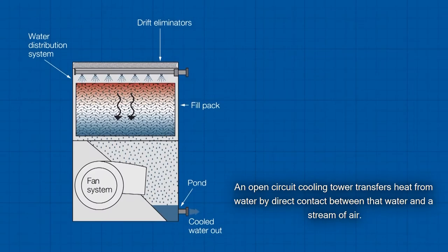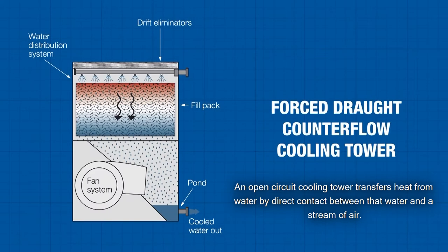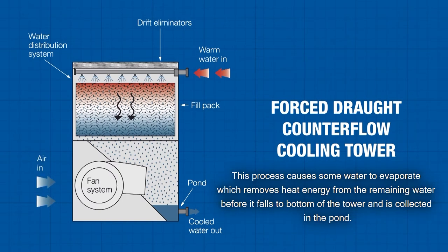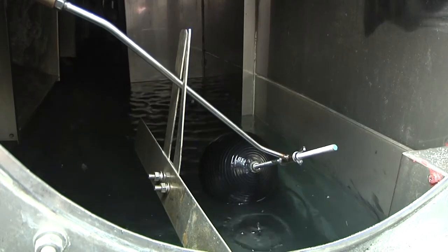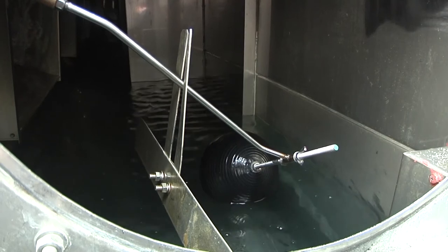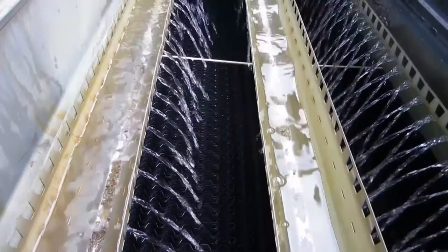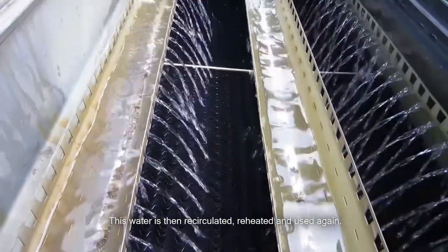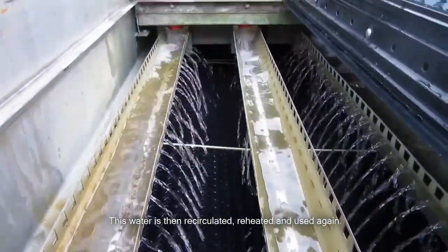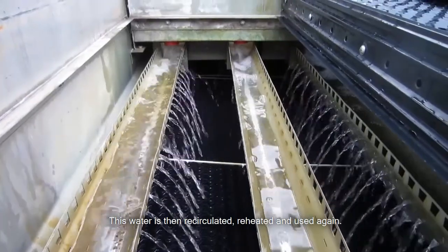An open circuit cooling tower transfers heat from water by direct contact between that water and a stream of air. This process causes some water to evaporate, which removes heat energy from the remaining water before it falls to the bottom of the tower and is collected in the pond. This water is then recirculated, reheated and used again.